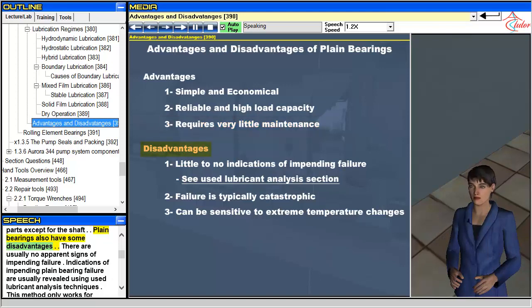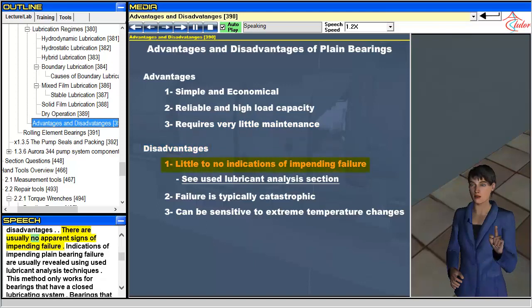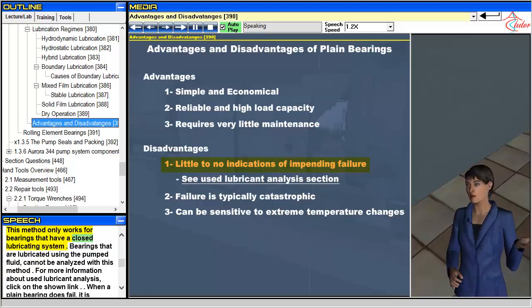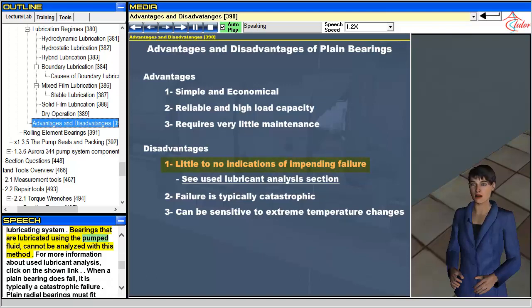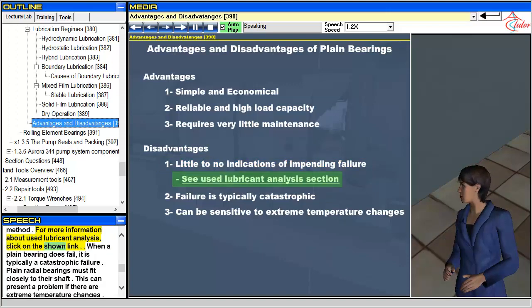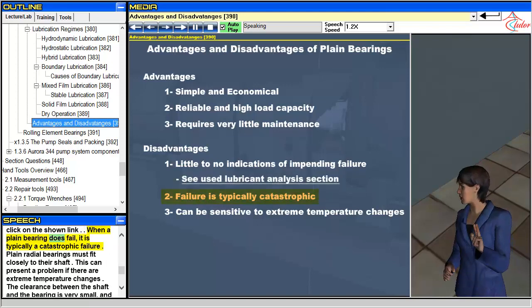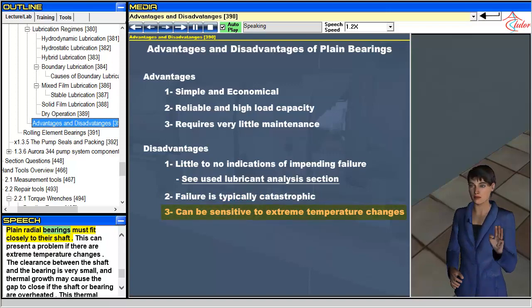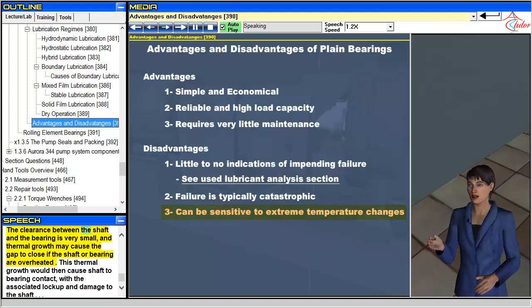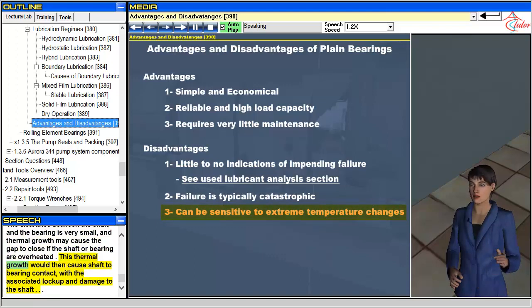Plain bearings also have some disadvantages. There are usually no apparent signs of impending failure; indications are usually revealed using used lubricant analysis techniques, which only works for bearings with a closed lubricating system. Bearings lubricated using the pumped fluid cannot be analyzed with this method. When a plain bearing does fail, it is typically a catastrophic failure. Plain radial bearings must fit closely to their shaft, which can present a problem with extreme temperature changes, as thermal growth may cause the gap to close and result in shaft-to-bearing contact, with associated lockup and shaft damage.